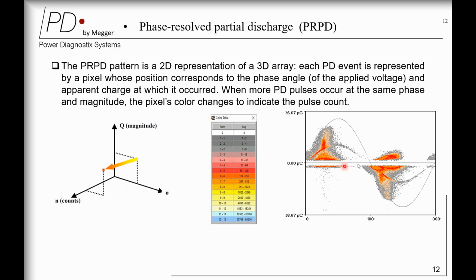This is my phase shift from 0 to 360 degrees of the applied voltage, and the apparent charge at which it occurs. The more PD pulses occur at the same phase shift and magnitude, that means the height, the more the pixel color changes to indicate its pulse count. If you have no PD, it is white. If you have some pulse count, it is gray, then orange, and depending on the intensity, the color code keeps changing.